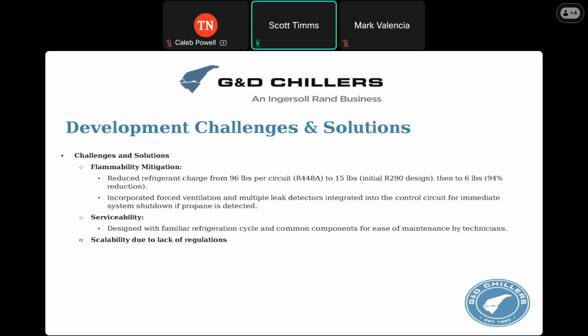So the standard 70 horsepower unit that we would have provided for New Belgium in this situation would have 96 pounds per circuit, so 192 pounds total of 448A. Our initial design, we removed some equipment, we moved some things around, took us down to 15 pounds per circuit or 30 pounds total. And then the final design had us at 6 pounds per circuit or 12 pounds total. So 94% total reduction. So essentially in one circuit, you have less propane than you do in like a propane tank that you would hook your grill up to. So really, really, really minimize the potential for danger there.